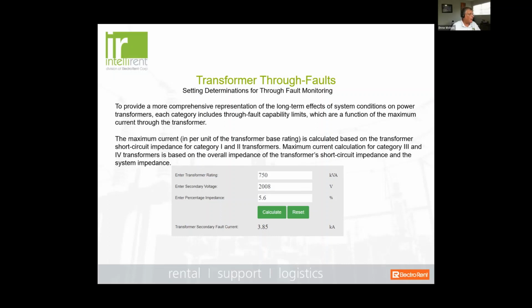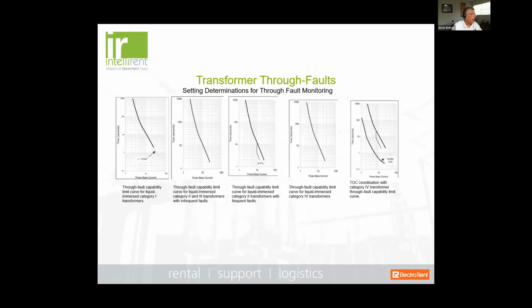So basically, we're looking at the maximum current in per unit of the transformer's base rating, and that's calculated based on the transformer short circuit impedance for categories 1 and 2. The maximum current calculations for category 3 and 4 transformers are based on the transformer's short circuit impedance plus the system impedance, which is all available on the transformer nameplate rating. If not, it's important to get advice from your transformer manufacturer on what those withstand capabilities are. If we look at the different categories of transformers, you'll see it involves the time, or the length of the through fault, and the multiple of the transformer's base current rating, in terms of the magnitude of the through fault. And you can see they're slightly different based on the category.